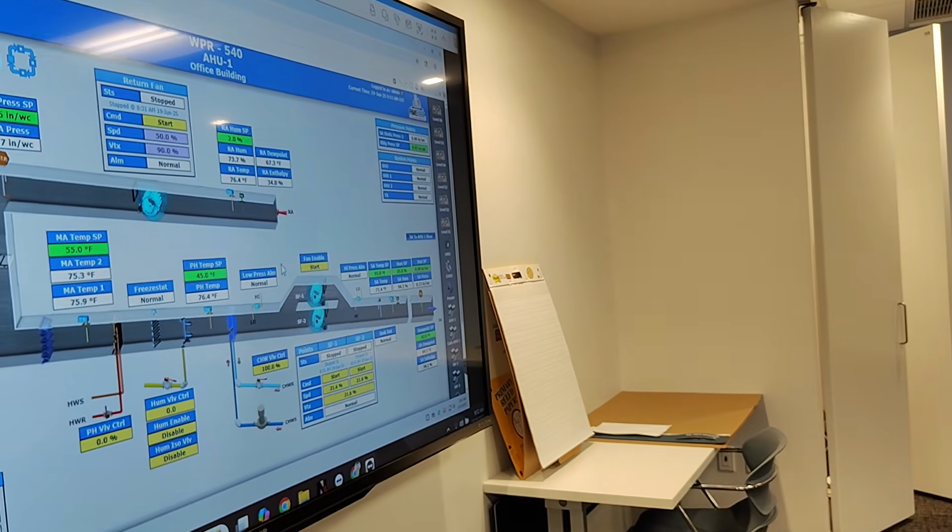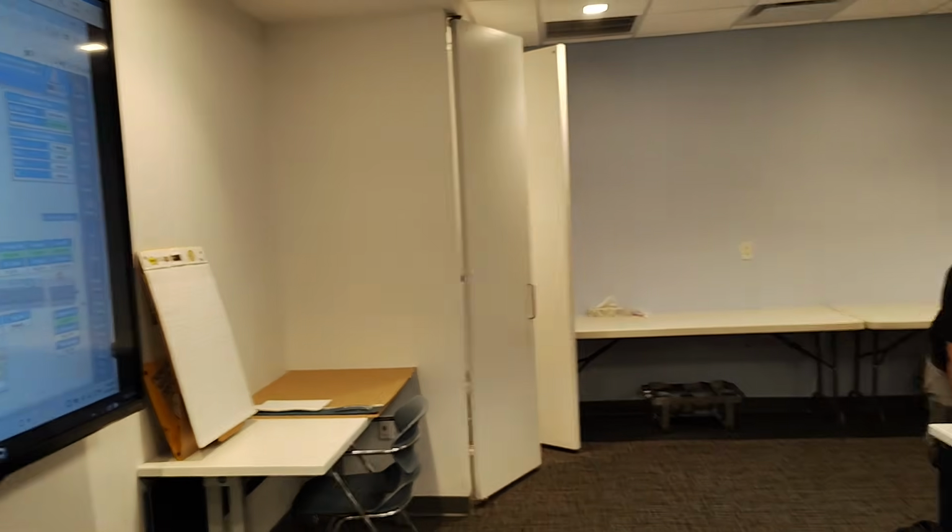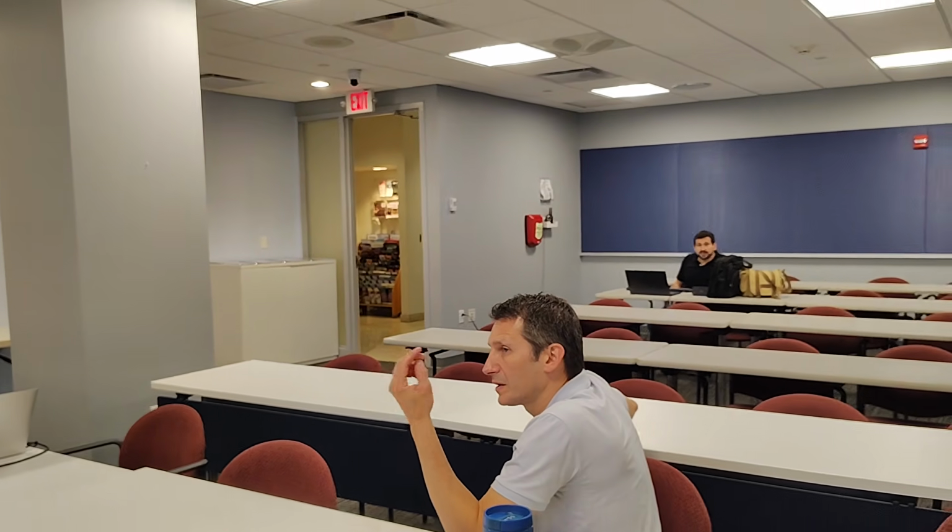Just on the set, it's taking some time. I mean, it's been sitting here at 0.12 all day, so that thing should have ramped up in the background, even overridden. So it's not ramping. 0.17. It moved. It may be moving. It's not doing what any of us would expect it to do. So they might be looking at other things that are prohibiting or allowing their controller to modulate that speed.